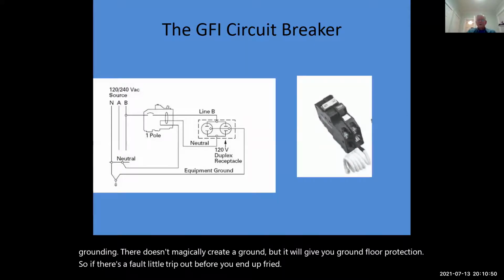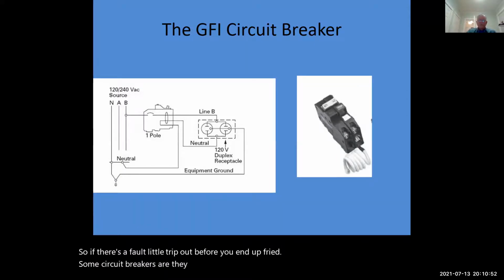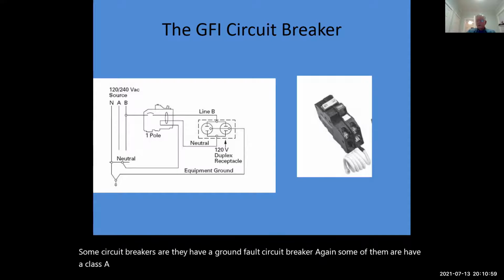Some circuit breakers are ground fault circuit breakers. Again, some of them have Class A ratings for the 4 to 6 milliamp trips. Some don't. So if you go that route, you should know what it is.